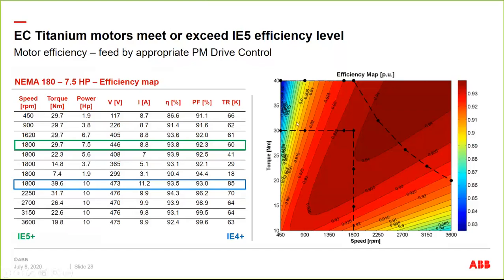So if I want to run at 2250, let's say I got 5 brake horsepower at 2250 RPM, instead of taking a 3600 RPM motor and slowing it down, we're saying take that 1800, overspeed it, even if you have to oversize the motor slightly to get the torque you need out here, you're going to be much better off because you're going to be operating in this constant efficiency island above base speed. So tune in later for that technology webinar where I'll go more into depth about that. But basically it's saying let's maximize our operating range above base speed so we don't have to operate as much below base speed where the efficiency starts to drop off.